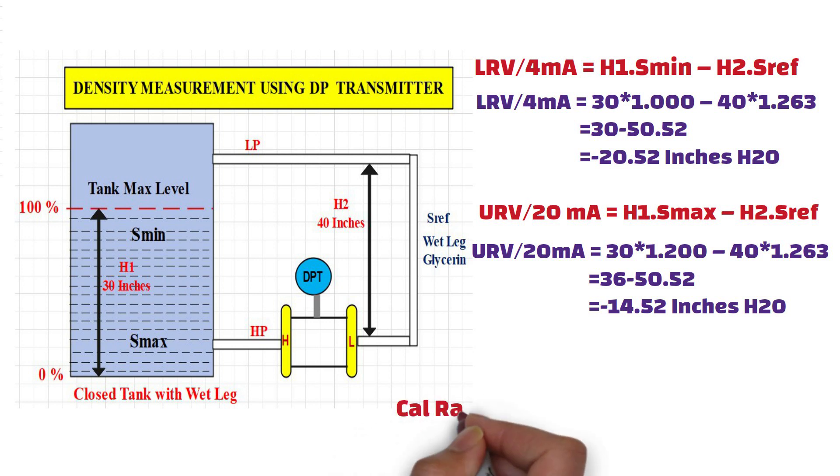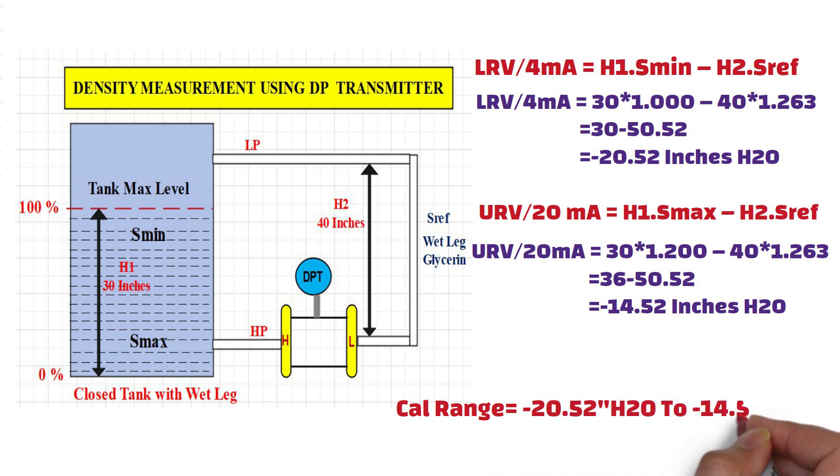So, DP transmitter's calibration range is minus 20.52 inches H2O to minus 14.52 inches H2O in this example. As I mentioned earlier in this video, these equations are valid only for constant level application.